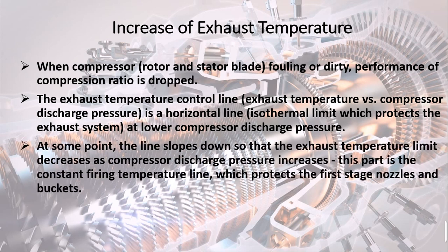At some point, the line slopes down so that the exhaust temperature limit decreases as compressor discharge pressure increases. This part is the constant firing temperature line, which protects the first stage nozzles and buckets.